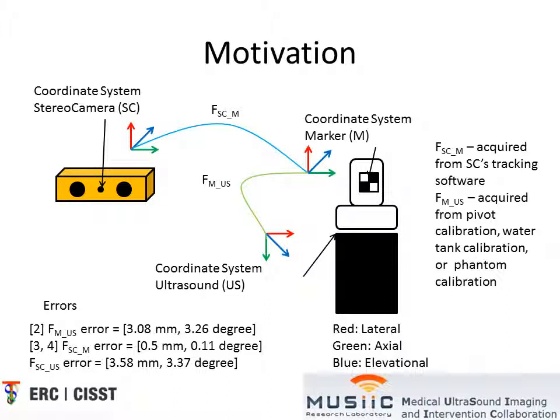The error in the stereo camera tracking software is sub-millimeter and is generally considered negligible in these applications. However, the transformation from the marker to the ultrasound must be acquired with a calibration process. Literature has shown that this process will generate errors of approximately three millimeters.